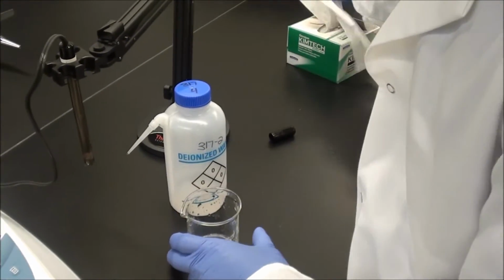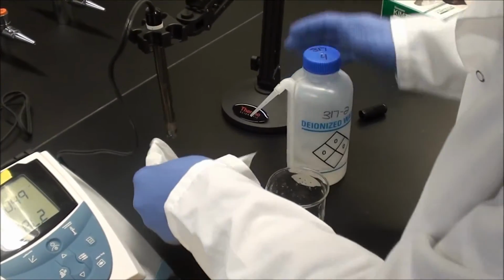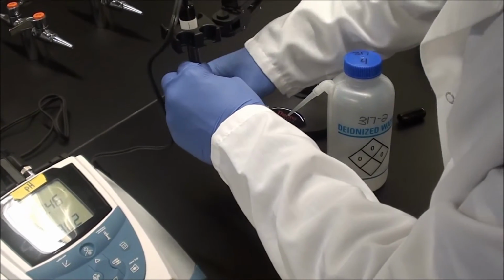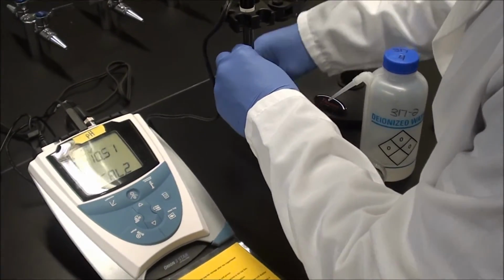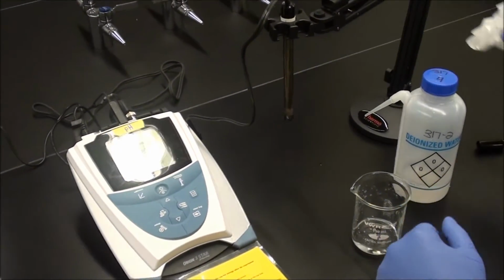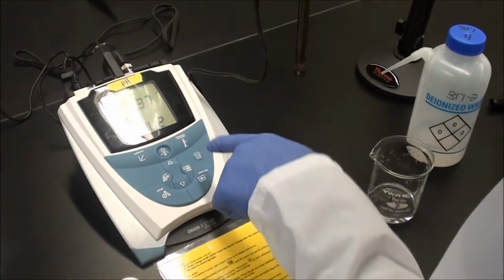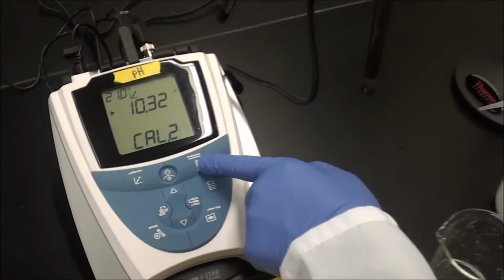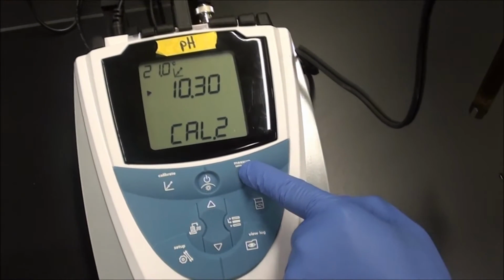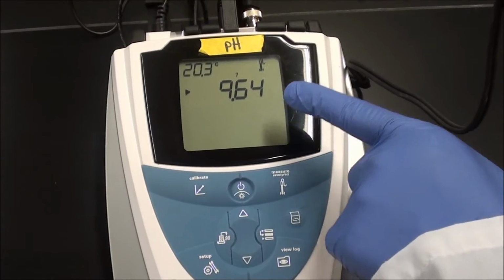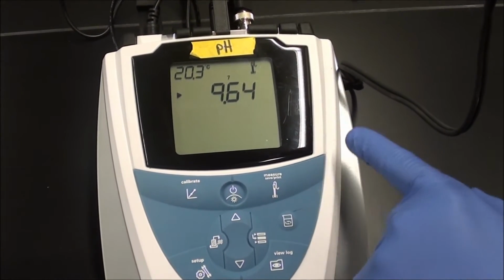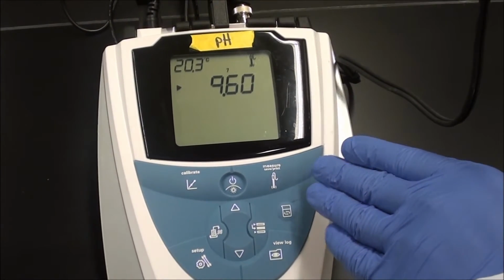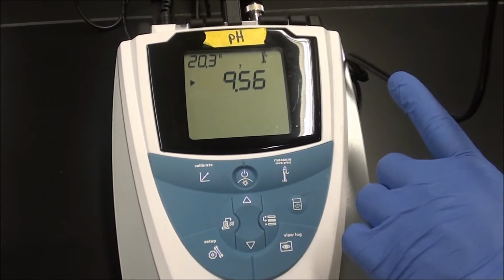And go ahead and wipe it off with some clean Kim wipes. So once you're done with the pH 10 buffer, you want to go ahead and press the measure button, which saves it. That means the pH is calibrated, but we still need to do one more step, which is to set the continuous measurement settings.